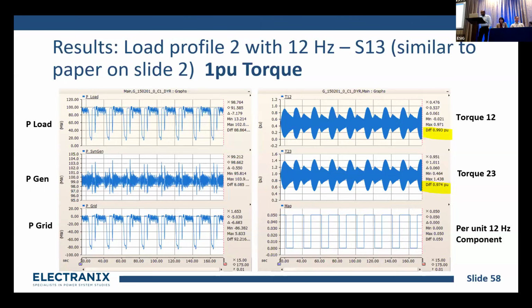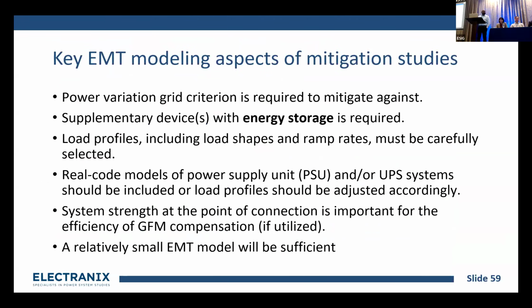So what are the key modeling aspects of mitigation studies? First of all, if you want to mitigate, we need to have something to mitigate against. So we need to have a requirement, otherwise without a target we cannot mitigate. Whether it's 10 megawatts or 20 megawatts, whatever the number is, we need that number published. Then we can develop a process to mitigate up to that number. Supplementary devices with energy storage are required. In other words, when we have this power fluctuation, the power goes up and down, so you need to fill that gap with something. When you fill that gap, you need energy storage.